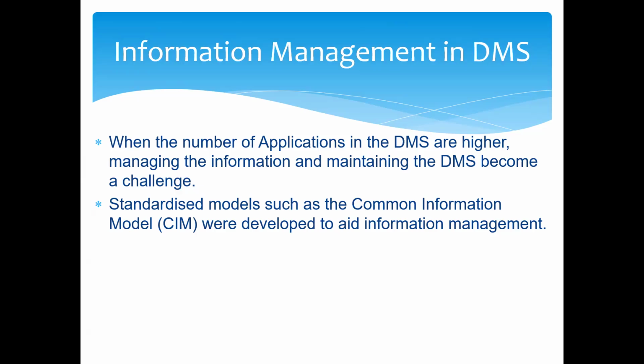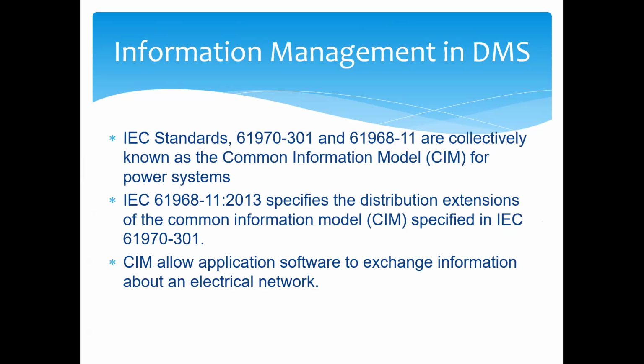If we consider the customer-wise data, voltage, current, and power consumption data, it's a huge information load. So maintaining such data is a challenge. For that, standardized models such as the Common Information Model were developed for information management. The IEC standards 61970-301 and 61968-11 are collectively known as the Common Information Model for Power Systems. And the IEC 61968-11 2013 version specifies the distribution extension of the Common Information Model, which is specified in IEC 61970-301.